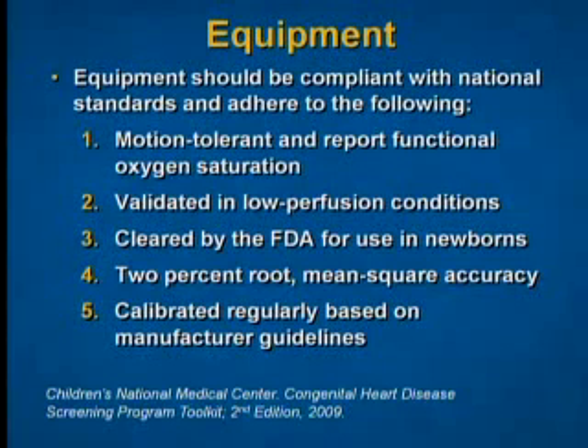And so included in the guidelines is information regarding the screening equipment. So the pulse oximeter equipment should be compliant with the national standards and adhere to the following. Of course, the pulse oximeter should be motion tolerant and report the functional oxygen saturation. It should also be validated in low perfusion conditions. It should be cleared by the FDA for use in newborns. And it should have a 2% root mean square accuracy. And then it also should be calibrated regularly based on the manufacturer guidelines.